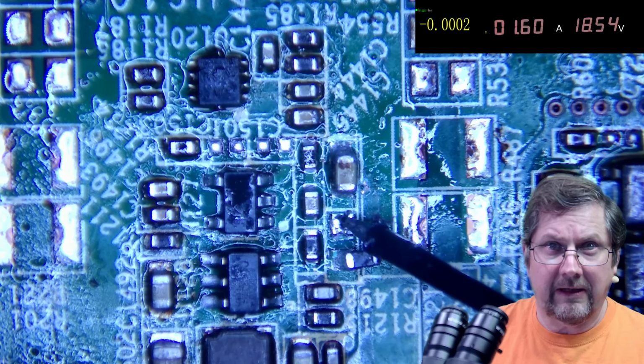And that's what we're going to troubleshoot next. We're going to try to figure out why it is that when I check my resistance to ground, coming on the other side where I broke this circuit, we've got 34 ohms, that's essentially a short. If I check in the domain over, notice the ohms are so high it's not reading. There we go, 0.88 kilo ohms. If I jump over to the next one, 892. So you can see that's the problem, right? I can keep going, but it doesn't really matter. The big problem is that whenever I touch to this point, I get 34 ohms.